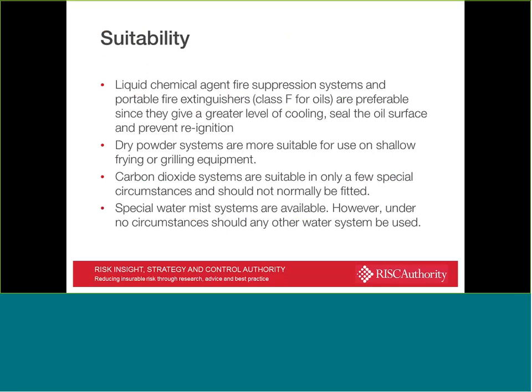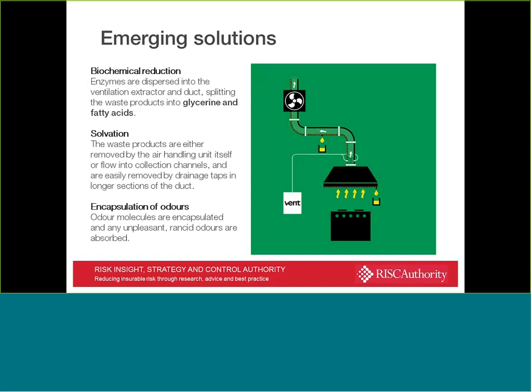Suitability of systems, you'll find a little bit of guidance on this in RC44. Which suggests that dry powder systems are more suitable for use on shallow frying or grilling equipment, carbon dioxide in certain circumstances, and that specialist water mist systems are available, but that you shouldn't necessarily use a water-based system where you've got cooking oils and fires, because they can just make the situation worse. And it recommends, in general terms, that liquid chemical agent fire suppression systems and portable fire extinguishers, in particular the class F extinguishers, are preferable, since they give a greater level of cooling, and they will seal the surface of the oil. The class F extinguishers use a saponification approach to basically turn the oils into a soapy-like substance which can no longer burn, which also helps to prevent reignition.